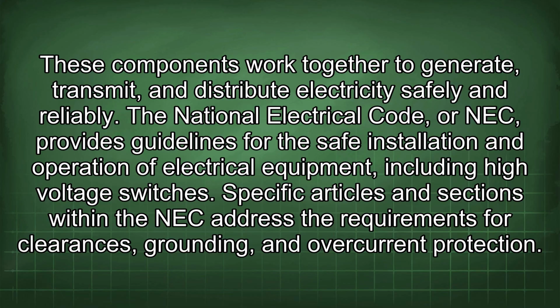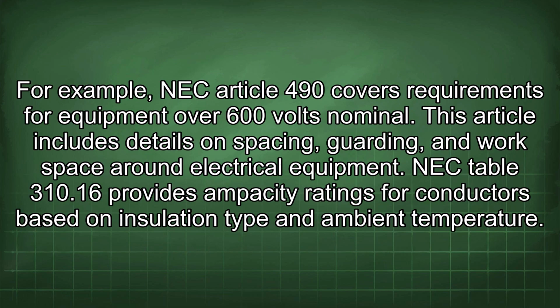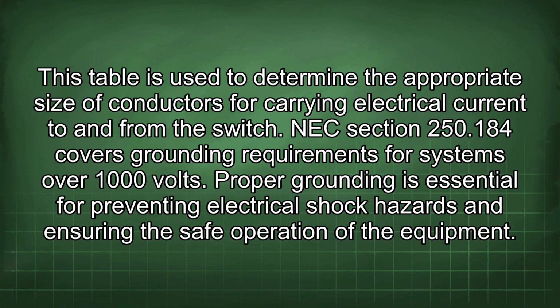The National Electrical Code, or NEC, provides guidelines for the safe installation and operation of electrical equipment, including high-voltage switches. Specific articles and sections within the NEC address the requirements for clearances, grounding, and overcurrent protection. For example, NEC Article 490 covers requirements for equipment over 600 volts nominal. This article includes details on spacing, guarding, and workspace around electrical equipment. NEC Table 310.16 provides ampacity ratings for conductors based on insulation type and ambient temperature. This table is used to determine the appropriate size of conductors for carrying electrical current to and from the switch.